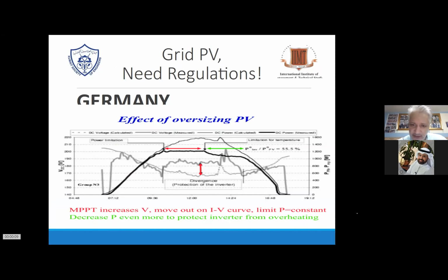The oversizing of the PV is, like I said to you, similar to the fuse. It's 1.27 to 1.5. In some desert areas, especially in America, most of them already use 1.5. So like a 15 kilowatt system with a 10 kilowatt inverter, or a 150 kilowatt roof with 100 to 120 kilowatt inverters, DC to AC, because it's known that they derate a little bit during summertime. And if they derate, you can see the cap on top of the system. When the power limitation kicks in, you can see a flat roof. Best is when these flat roofs occur only maybe 10 or 20 days max in a year. That's still okay. If it's more, we have to think about something.